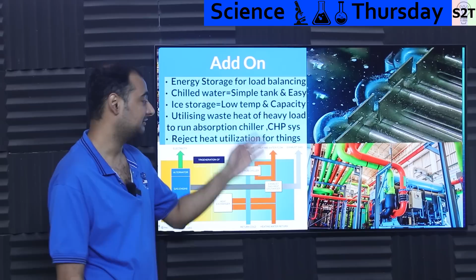But when you're talking about a power plant, you already have the waste heat, so you don't have to worry about it - you can just utilize it. In that scenario, say your district cooling requirement was 1 gigawatt and you're only getting 900 megawatts from waste heat, you'd put in 200 megawatts of electrical chillers just to buffer things out. So it does work - it's what we call a combined heat and power system, or combined heating and cooling system.